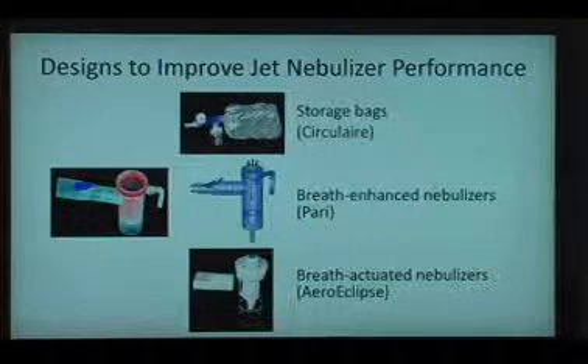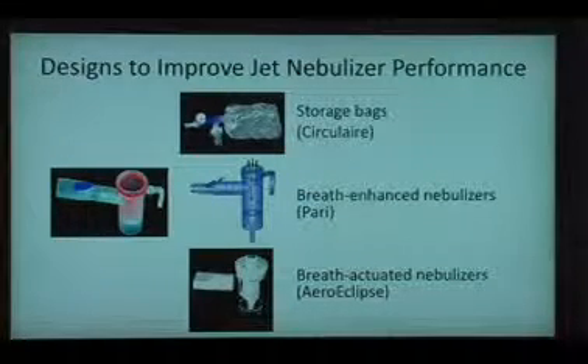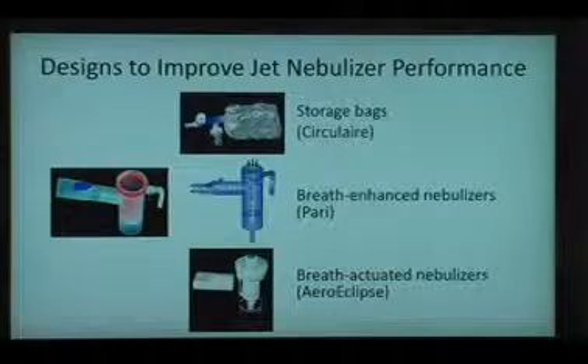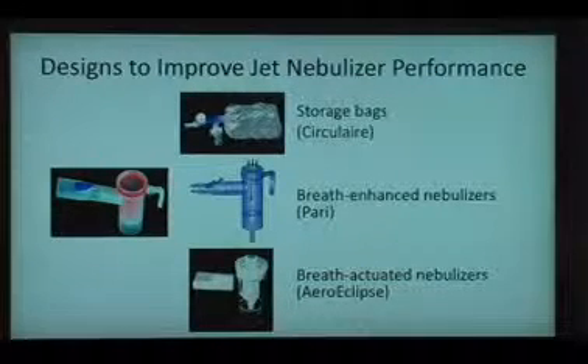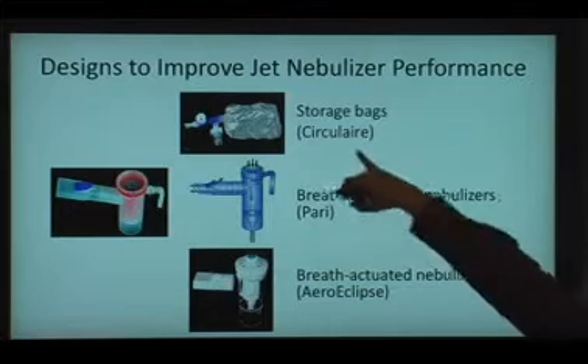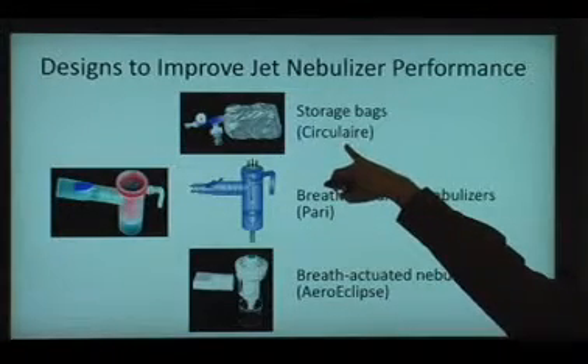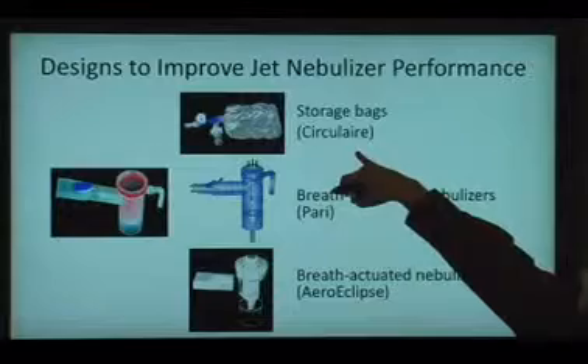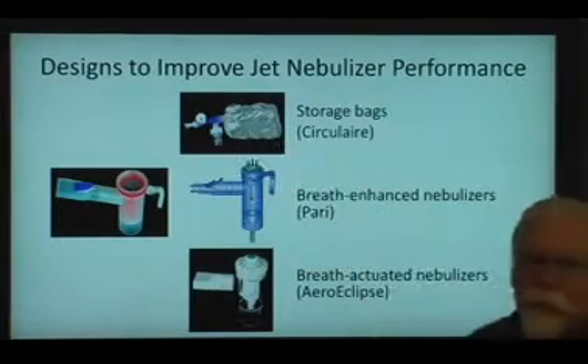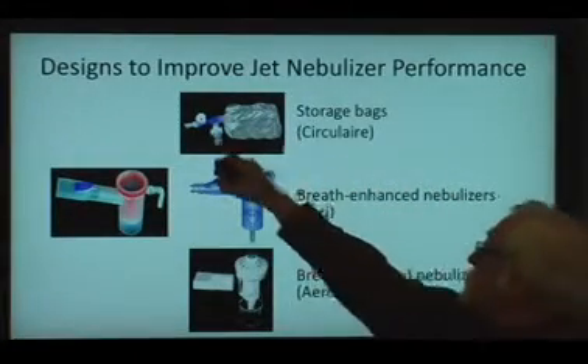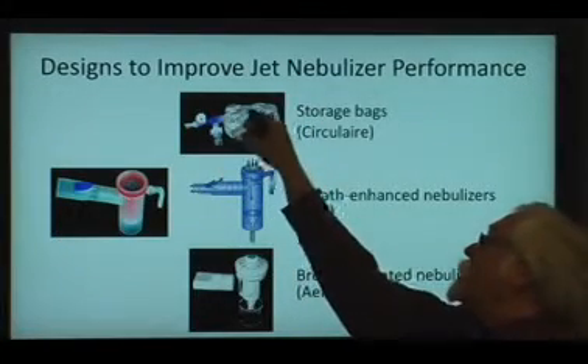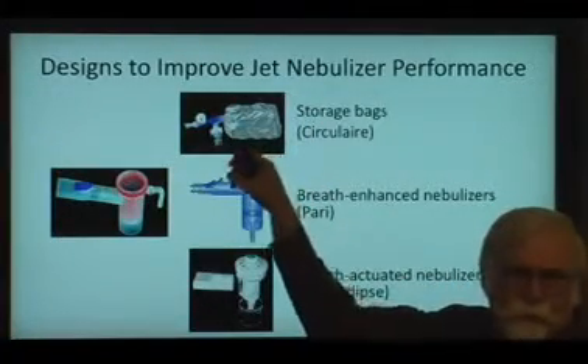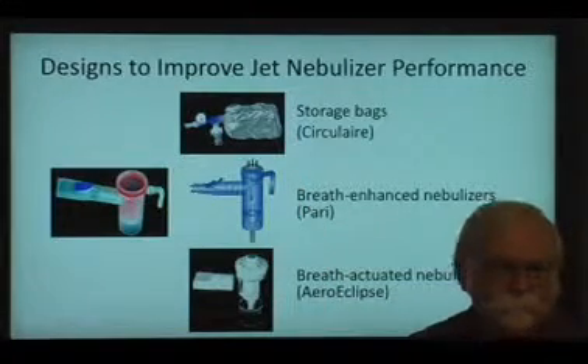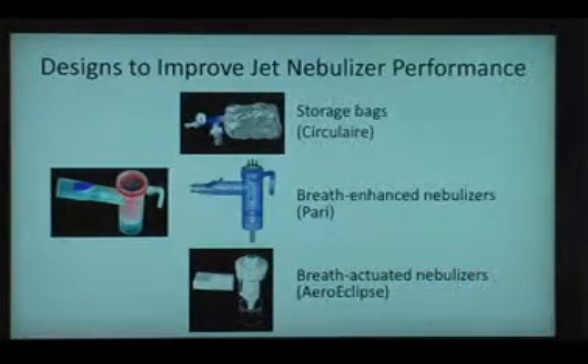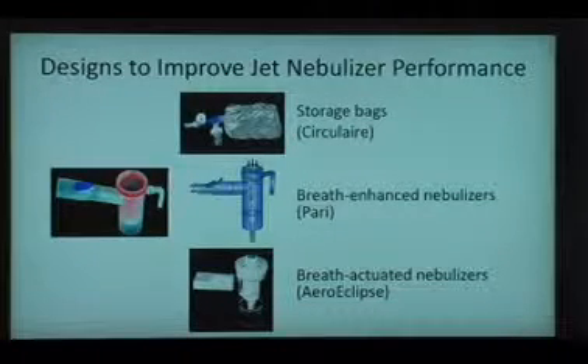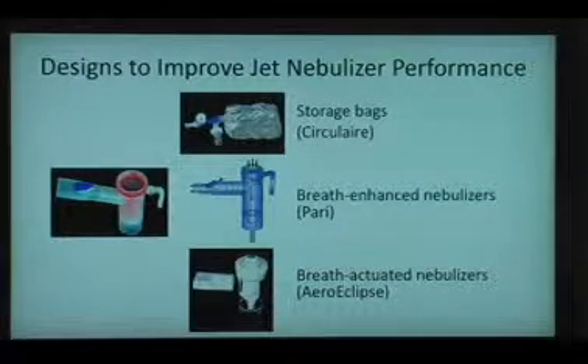Now, over the years, there have been a number of designs that have become commercially available in an attempt to improve jet nebulizer performance. So one design is the Circulaire, which I don't think has ever become very popular, but it is still commercially available, that uses a storage bag so that during exhalation, the aerosol, rather than blowing out into the room, goes into this bag, and then the patient inhales it on the subsequent inhalation. So that's a clever idea. I think it adds a fair amount of expense, and probably for that reason it's never become very fashionable.